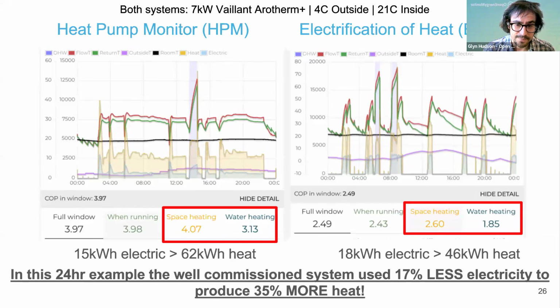So this is examples of two heat pumps with the data on our system. On the left we've got a heat pump from HeatPumpMonitor, and on the right we've got one from the electrification of heat. Both of these heat pumps are exactly the same. They're both 7 kilowatt Vaillant aroTHERM plus heat pumps. They're good heat pumps, which generally have good control systems, but we can see here that the differences in how one heat pump is set up make a considerable difference. Both of these heat pumps over this 24-hour period were running with the same outdoor temperature of 4 degrees, and they both had 21 degrees inside the house.